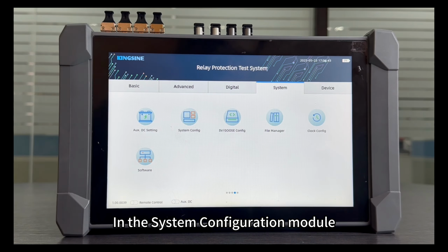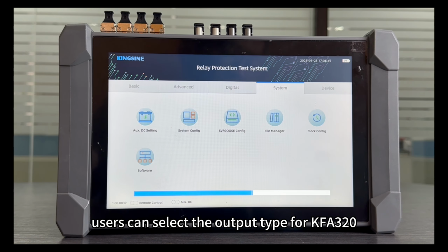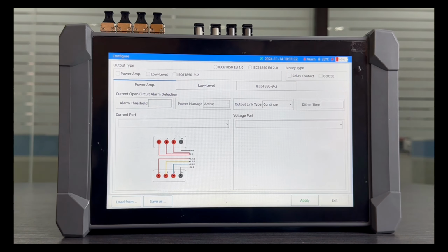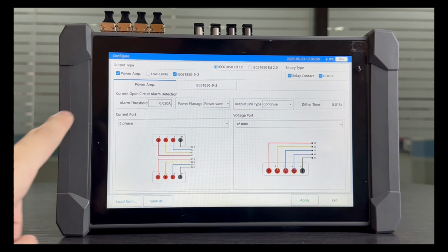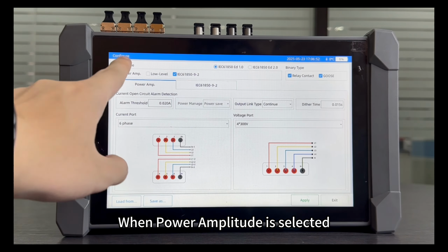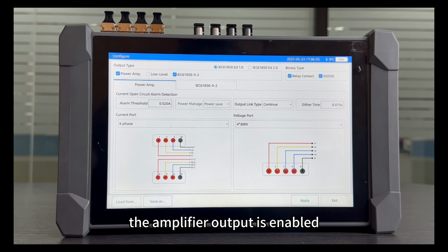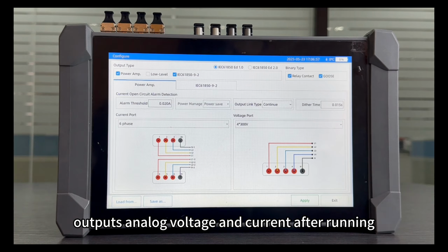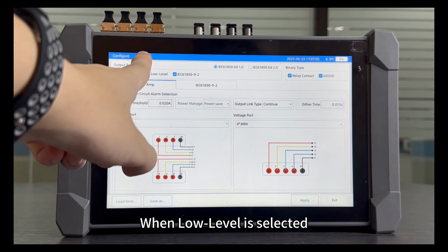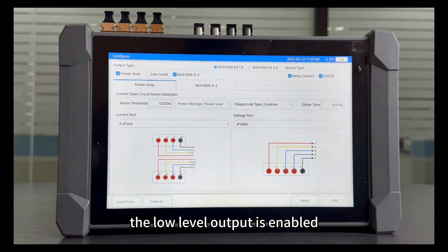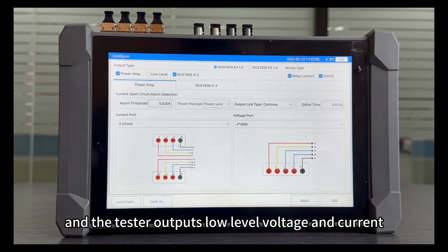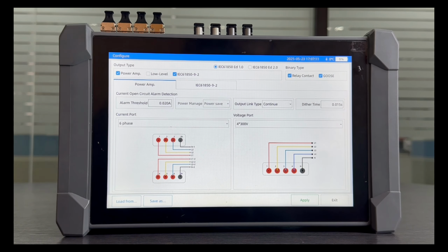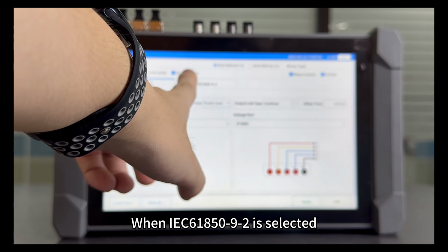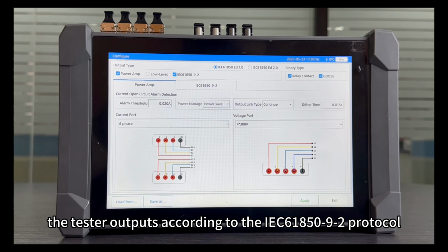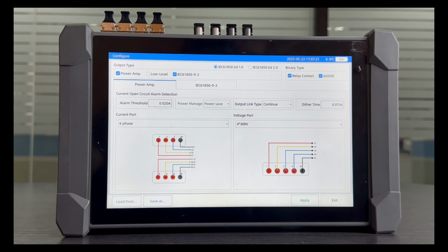In the System Configuration module, users can select the output type for KFA320. When power amplitude is selected, the amplifier output is enabled, and the tester outputs analog voltage and current after running. When low level is selected, the low level output is enabled, and the tester outputs low level voltage and current after running. When IEC 61850-9-2 is selected, the tester outputs according to the IEC 61850-9-2 protocol.